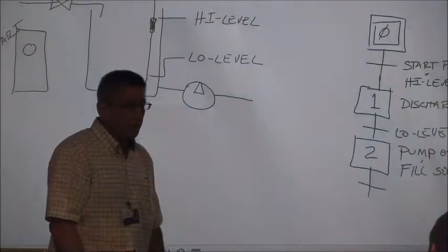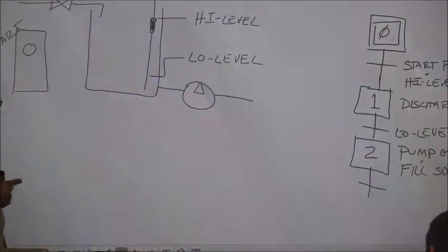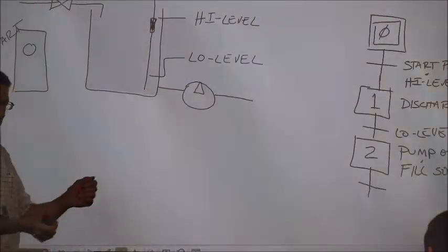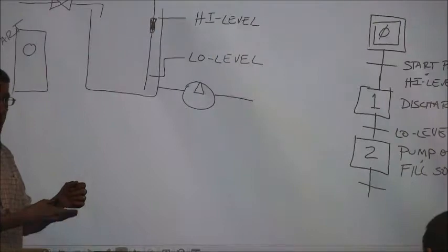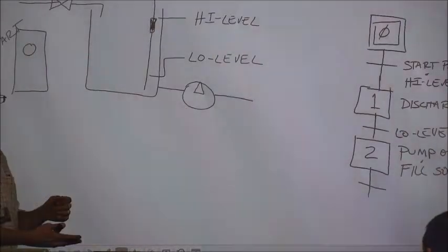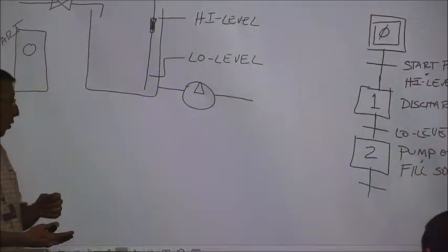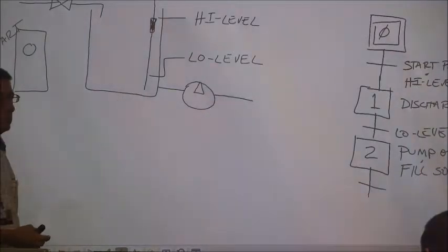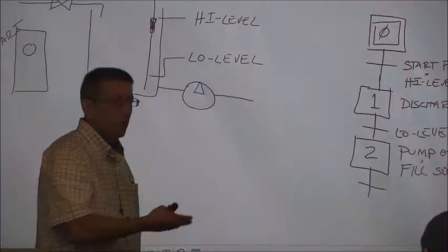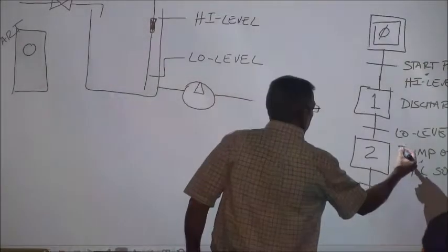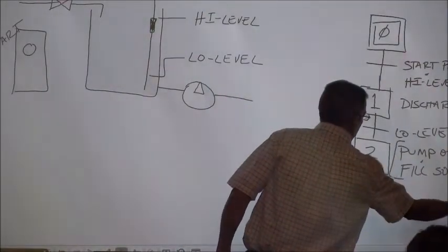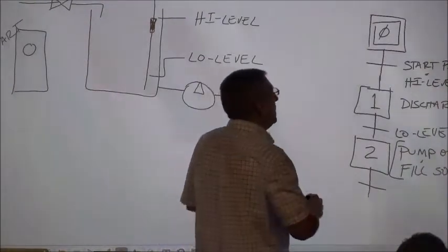If anybody's in any kind of a factory environment, you open up your electrical prints, the first few sheets are going to be a sequence of operations, right? Index, sequence of operations, or GRAFCET. And then after that, power circuit, control circuit. So yeah, we can do 2 actions in one.